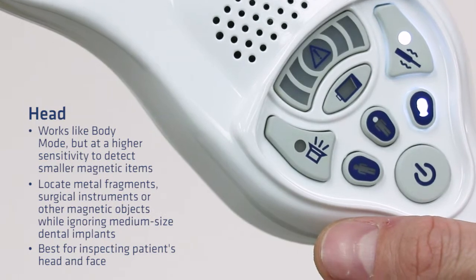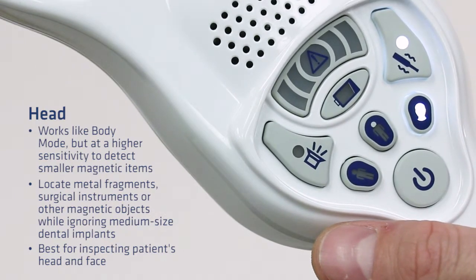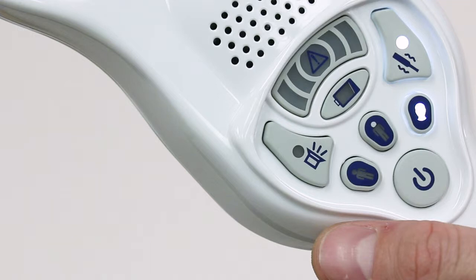This mode works in the same manner as the body mode, but it has higher sensitivity to detect even smaller magnetic items. For this reason, it's useful for locating metal fragments, surgical instruments, or other magnetic objects without detecting medium-sized dental implants, making it best suited for inspecting the patient's head and face. You may find that the different modes have benefits outside of their intended purpose. For example, if it is known a person has no prosthesis in their body, use the head mode to scan their body at a higher level of sensitivity than the body mode.